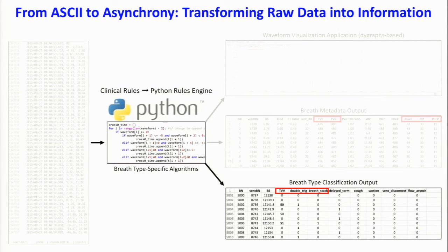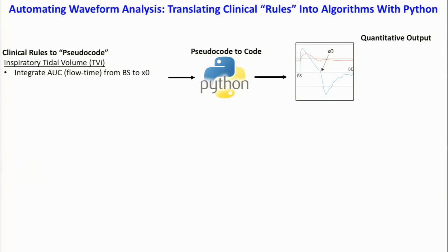And then finally, we have a breath type classification output. In this case, again, breath number on the x-axis of this table, and then each of the different subtypes, either a tidal volume violation or different subtypes of patient-ventilator asynchrony or common clinical artifact. And we can classify these breath by breath throughout all, let's say, 40 to 50,000 breaths that the patient may be taking per day. So how we do this from an algorithm perspective is pretty straightforward.